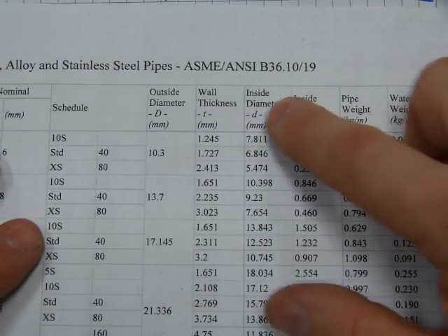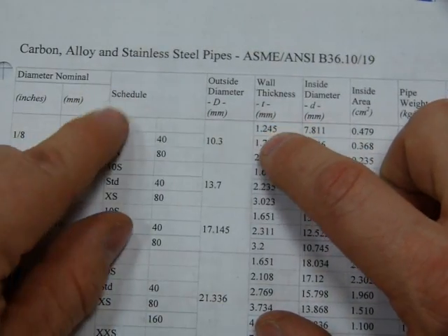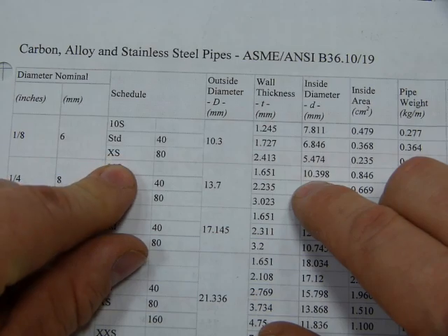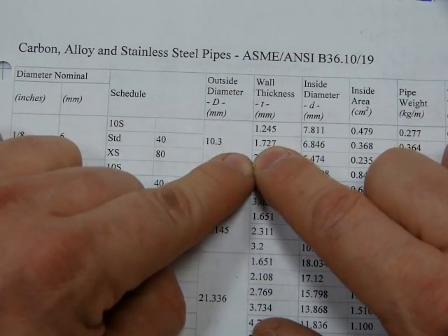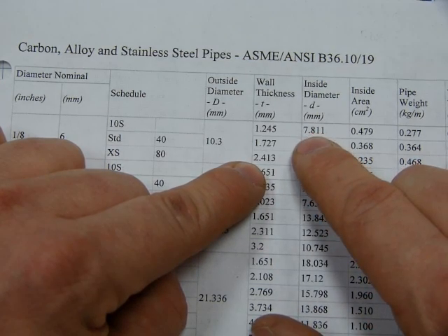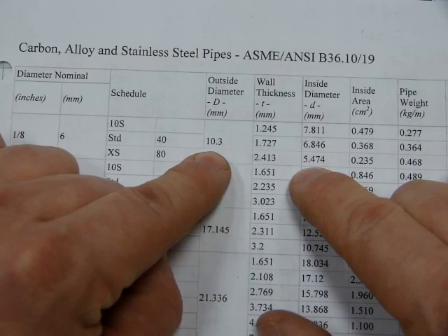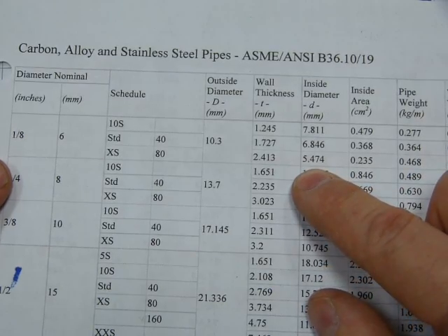It's really hard to measure it with a tape measure because it doesn't bend easily to it. Best thing to do is look it up in a pipe schedule, and you can see that all of the different pipes with all of their different schedules, 10S, they have different inside diameters, and you can see as the wall in a pipe is getting thicker and thicker, the space inside, the inside diameter, is getting smaller and smaller and smaller. It is because the outside diameter doesn't change. So if the walls are getting thicker, the inside must be getting less and less, and it does.